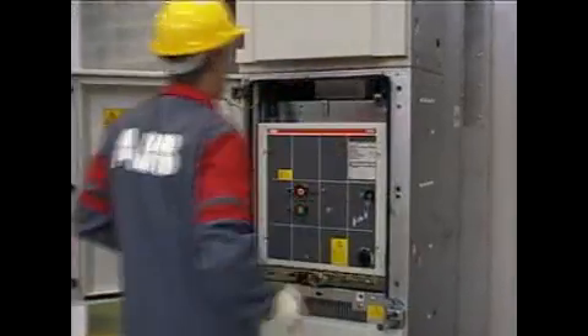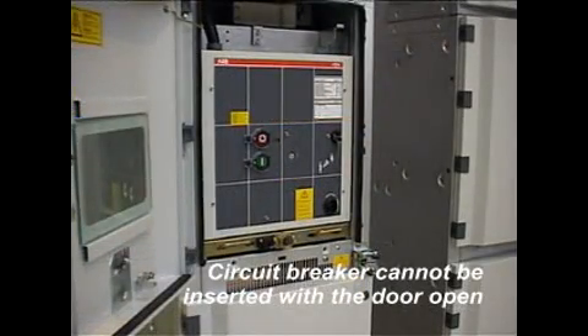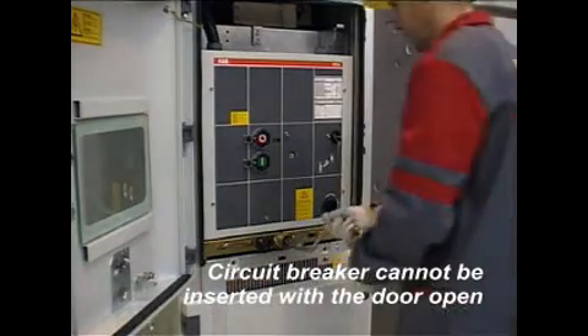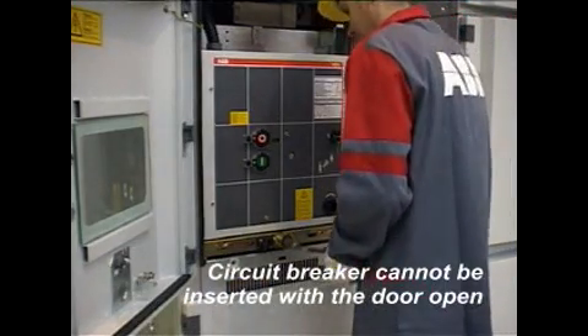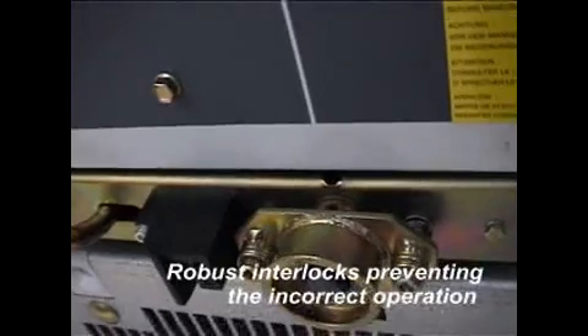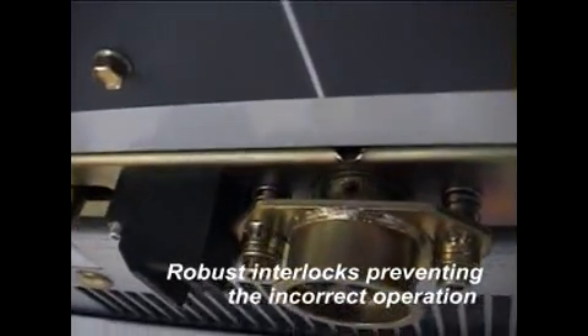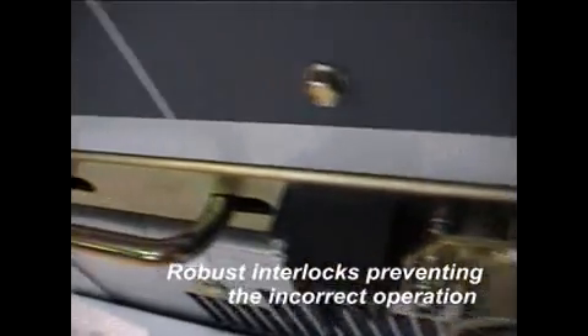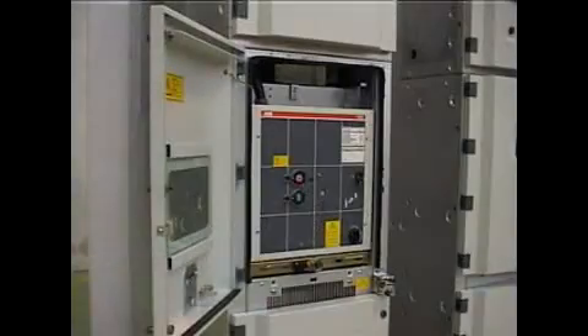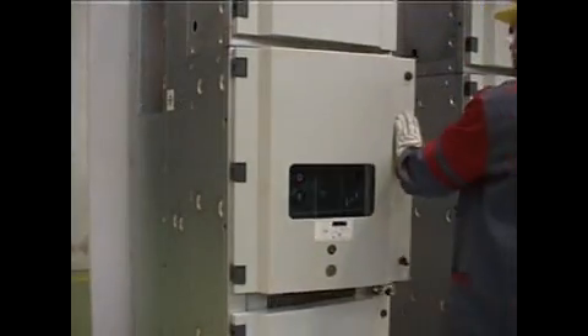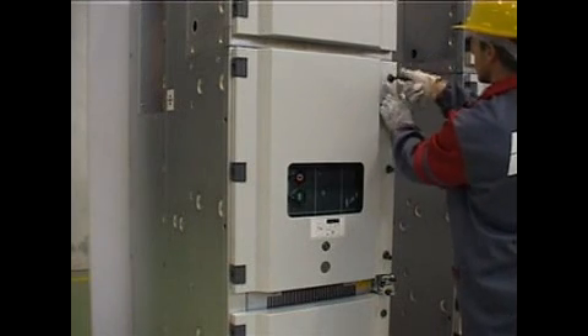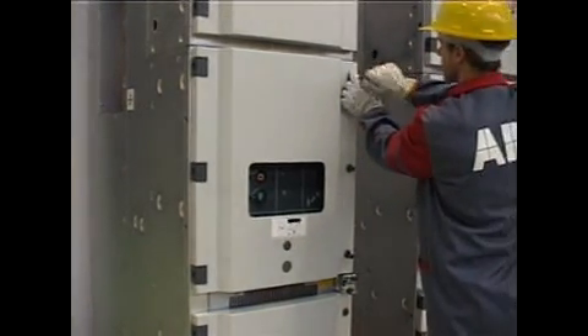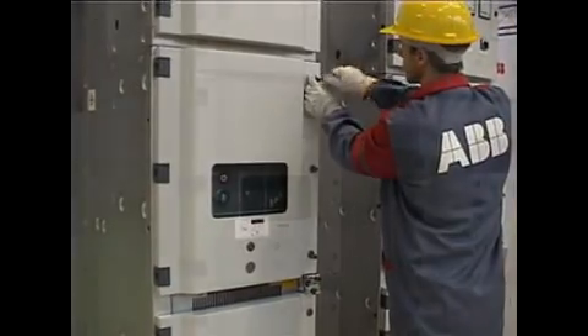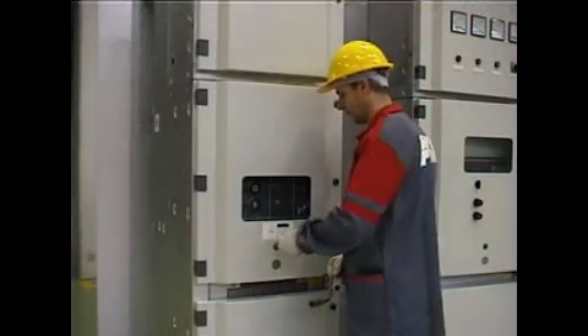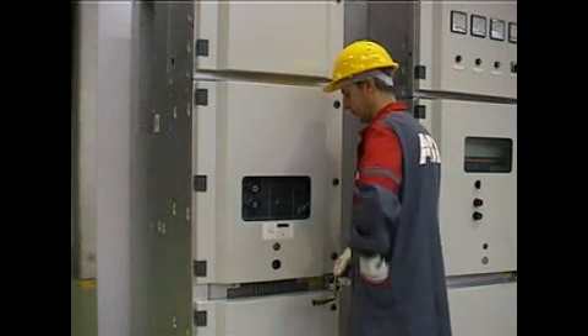At this point, the circuit breaker cannot be inserted with the door open because this could lead to a dangerous situation in case of a fault. This lock is achieved on the circuit breaker shaft, thanks to a stud located on the door. With the door closed, we can safely insert the circuit breaker in the cubicle.